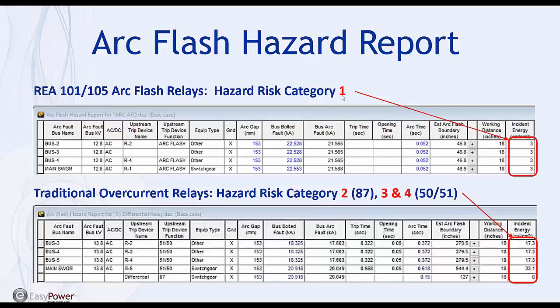It's a hazard risk category of 1, which is formerly what it was called. Now it's a calorie rating. But the idea here is that hazard risk category 1 is a very low, very safe rating. So that's what we're trying to achieve. You can see here with the other devices, you have a differential, you have overcurrent devices, and you can see that the incident energy is much higher, and you're into category 2, 3, and 4. So you can see that this isn't ideal, and we talked about before, overcurrent relays are too slow, and to provide the best possible protection for our personnel and prevent damage, having an arc flash system is absolutely essential.